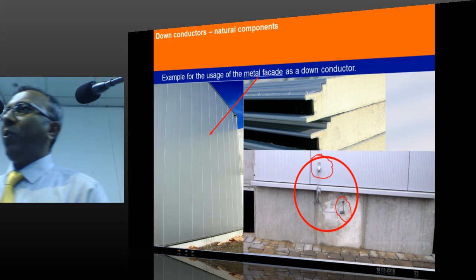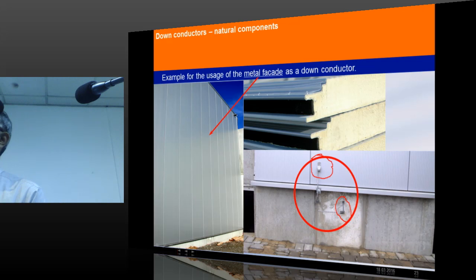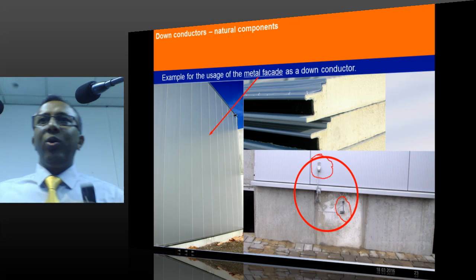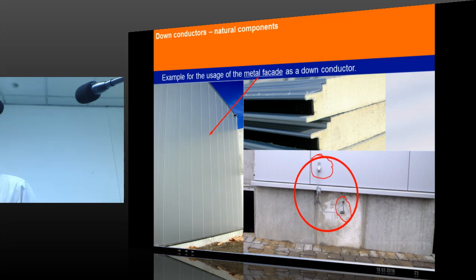If you provide a down conductor, sometimes insulated with a small bush, it is of no use. I don't know what is done in Sri Lanka, but in several places what engineers do is, even if the building is steel, down conductors are run with a small insulator. This will not do the job. What is required is that you connect the steel as a part of your protection.